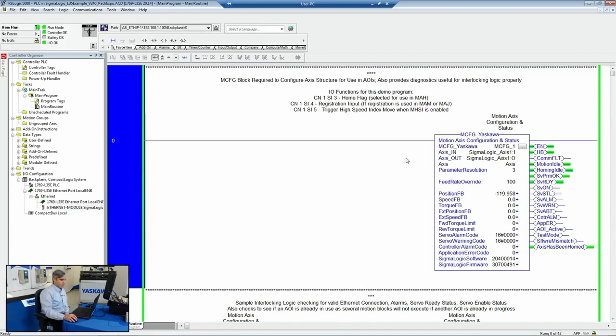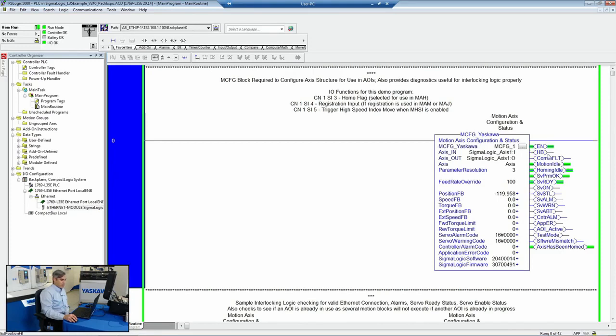So there's a few AOIs that are necessary to get the axis communicating with the Rockwell PLC. The first one's going to be the MCFG function block. That gives you status information of the Sigma Logic, such as position, torque, and speed. There's also a heartbeat, so if communications has failed, the drive will turn off.